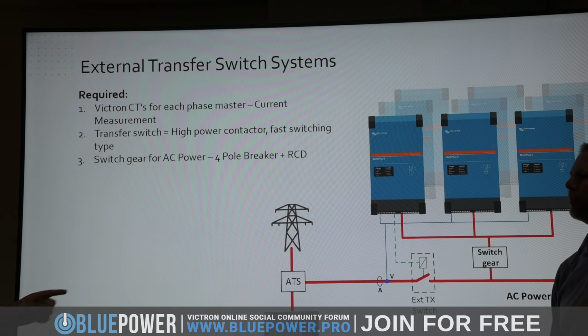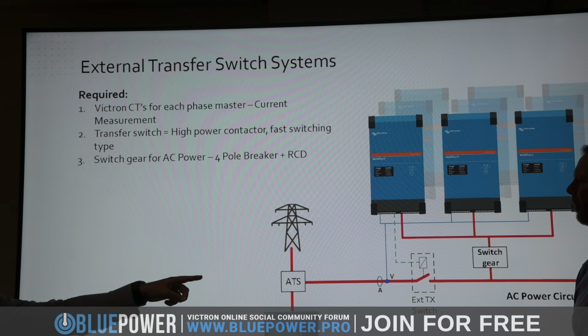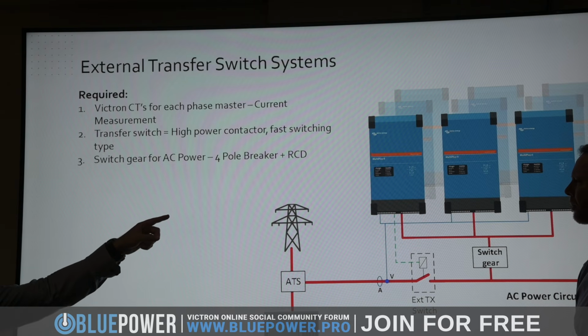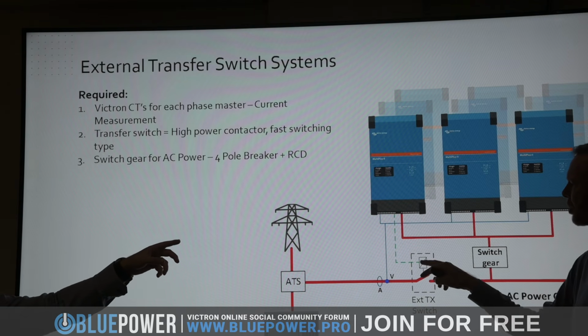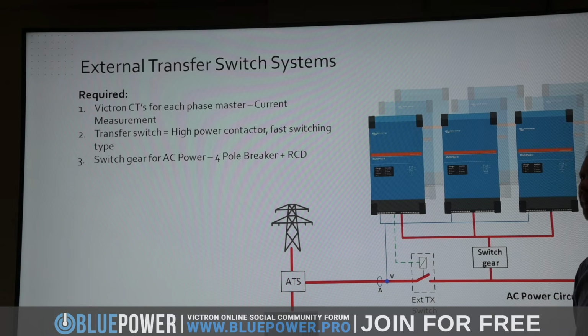You're also limited on the distance between the external transfer switch and the inverter - that's just a coil with 30 volts, that's the limiting point. You only need the external switch to the Multiplus, not the Quattros - the Quattros you can't use as this topology, it's different.